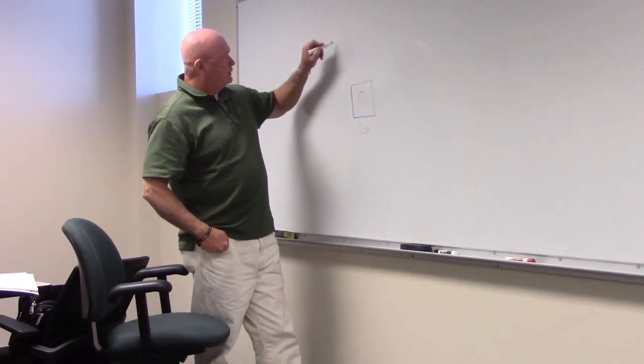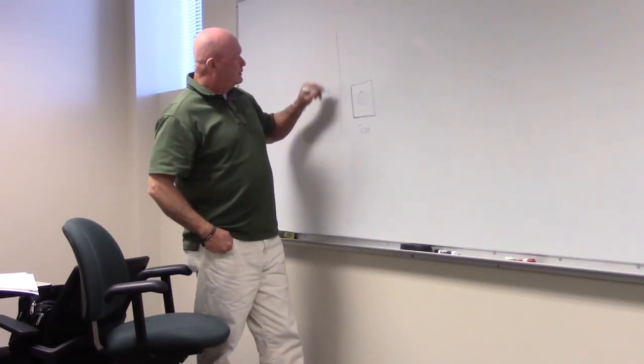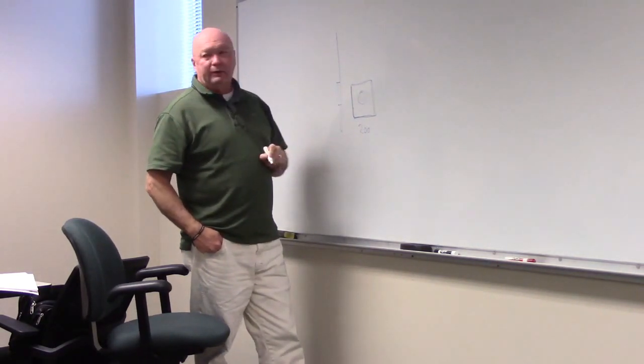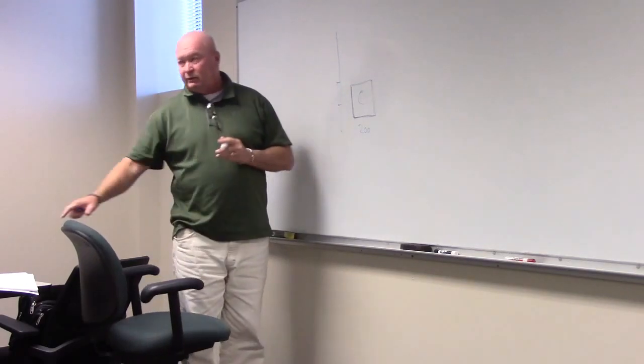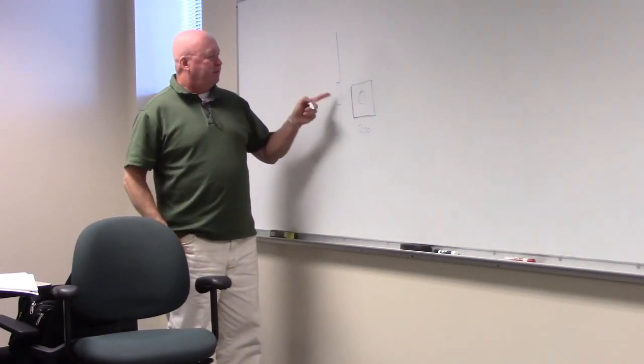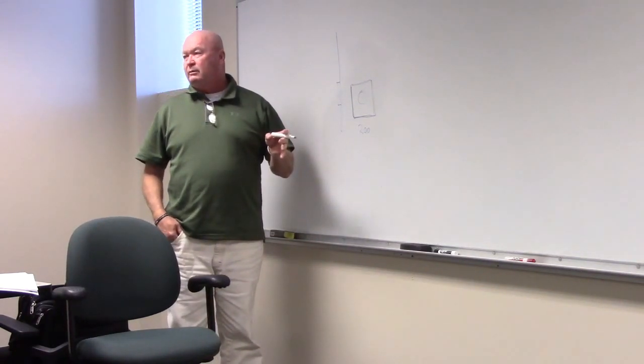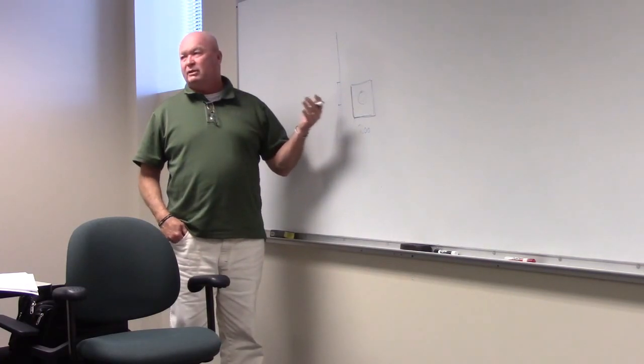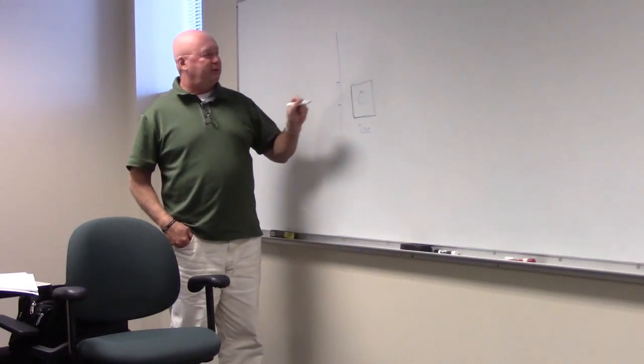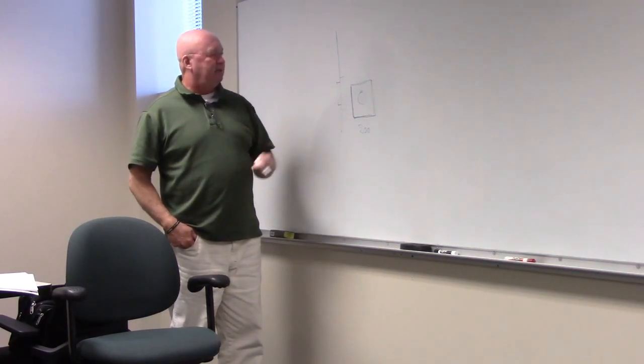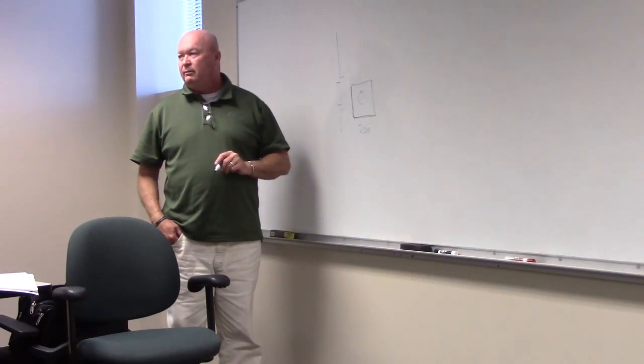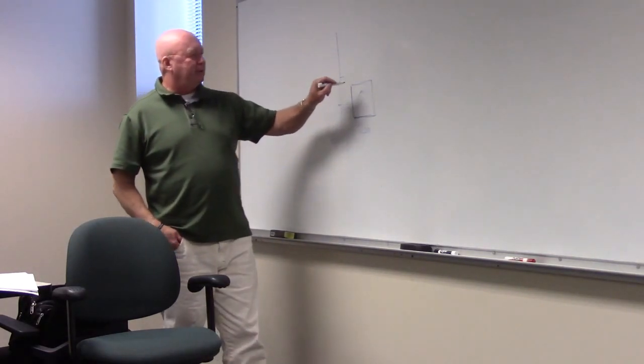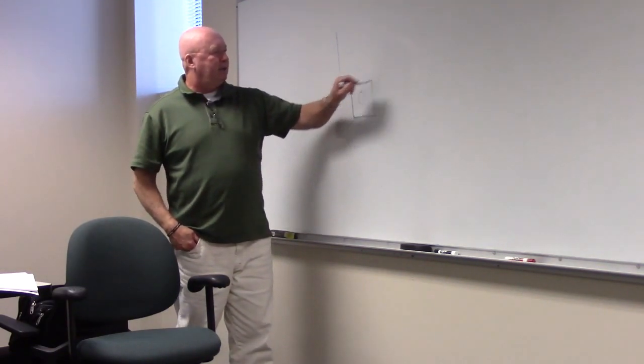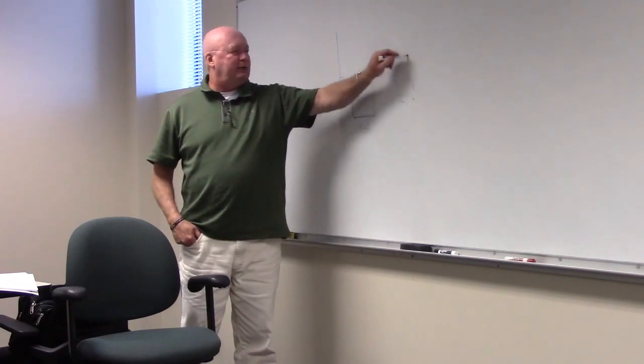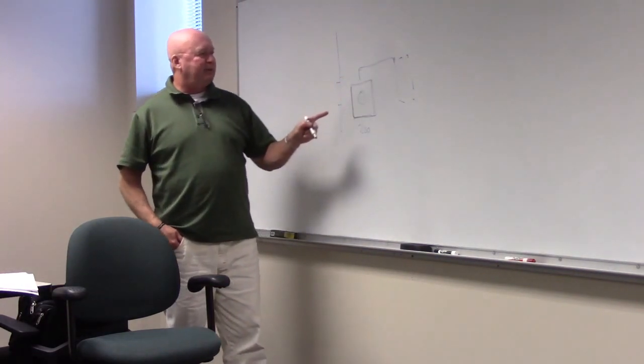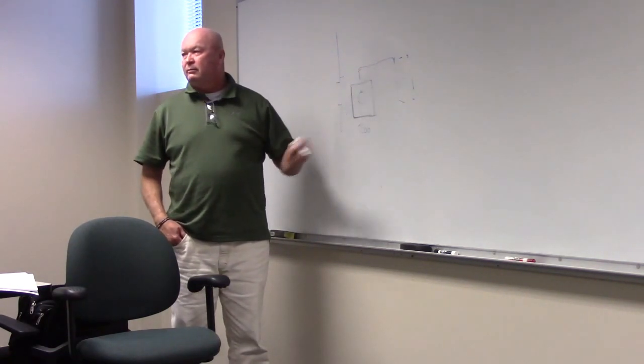Now here's the thing, if we're looking at this at our home, sideways, and that's our meter, for us to be able to put a meter on the outside and not have any type of main disconnect, and this is commercial or residential, it doesn't really matter, you must put the electrical panel directly behind the meter. In other words, you couldn't come out of this meter and set the panel 10 foot down the wall, because this is unprotected wire. It makes sense.